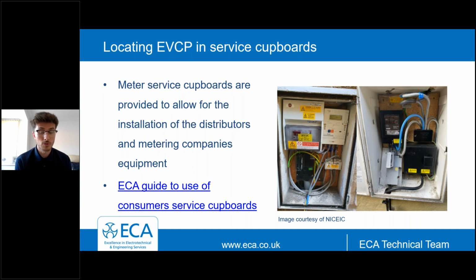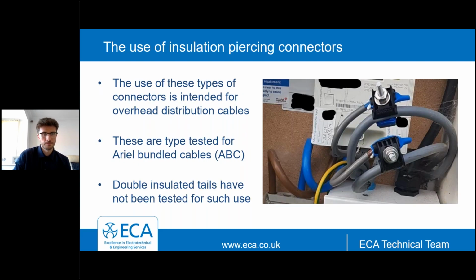And it may be that 2-3 years down the line, after carrying the installation out, you're getting a call back off your client because you now need to move this equipment. Again, ECA have a guide available to members on the use of consumers' service cupboards. Okay, so the next point I'm going to look at is the use of insulation piercing connectors.